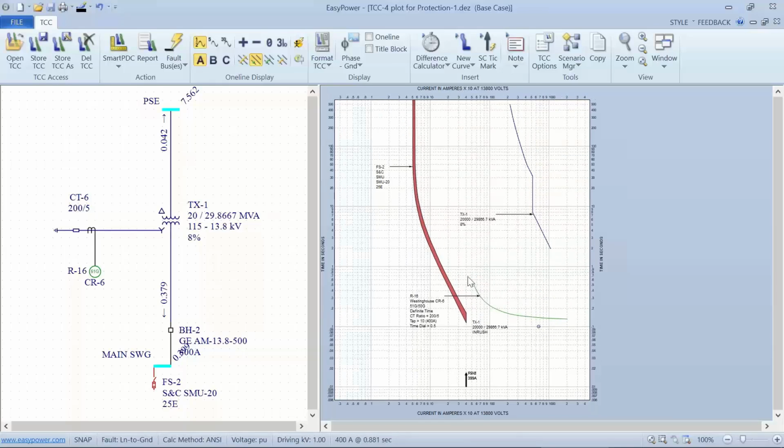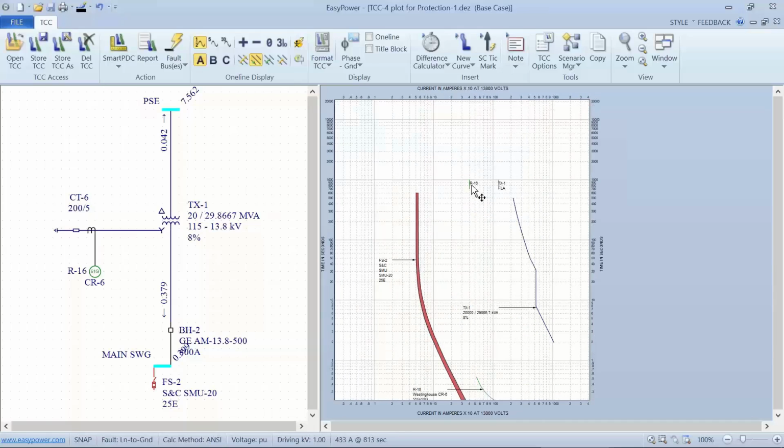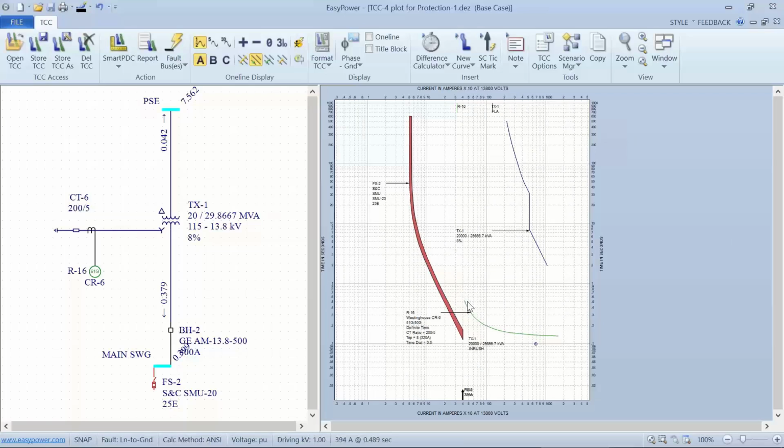This is showing that it's going to be picking up right at 524, so I missed the boat. Now it's picking up at 461. So again, the clipping is probably the second or third most common mistake, and you just watch me muddle through it. And so this gives us a possibility, now if I'm happy with that particular setting, of going back and closing this.